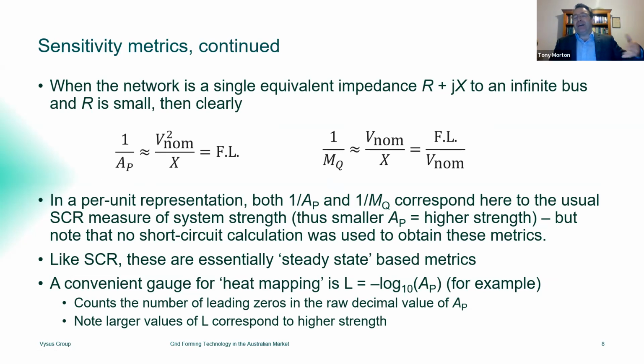And when we abstract to the very simple case of a network modeled by a single equivalent impedance, and we assume that impedance doesn't have too much resistance in it, we can relate those sensitivity coefficients directly to the traditional fault level that we get from a short circuit analysis. But the advantage here is that when we do these sensitivity calculations, we're not actually applying short circuits in the network and measuring fault currents. We're actually just doing incremental power flows and looking at sensitivity coefficients, but we're getting the same numbers out of this. And that's really the key here. So that allows us to talk about quantitative metrics of system strength that don't depend on the precise behaviour of fault current from different kinds of technology.